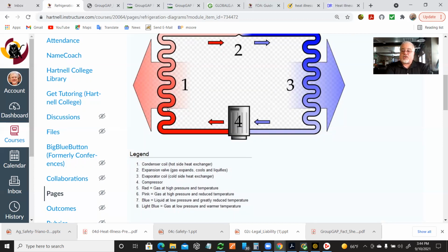And that's why sometimes refrigerators just don't work in the garage, because the garage is so dang hot. There's no insulation, especially if you're in a hot place. You're in Bakersfield, you're in Yuma, Arizona, someplace where it's really hot. You stick a refrigerator in the garage. It overwhelms the ability of this condenser to get rid of heat into the hot room. They work fine in the house because they're designed to work under 80 degrees. If the room's under 80, it can handle it. If it goes over 80, most refrigerators can't handle it. They're not designed to be able to get rid of heat here.